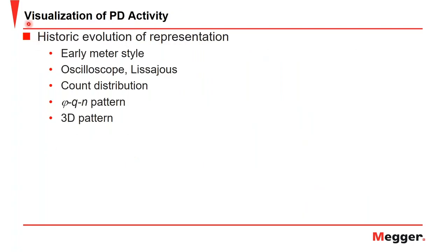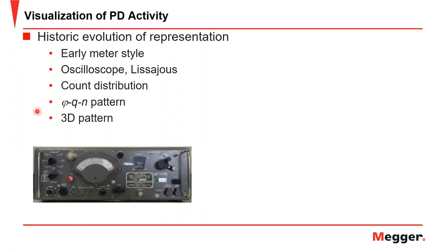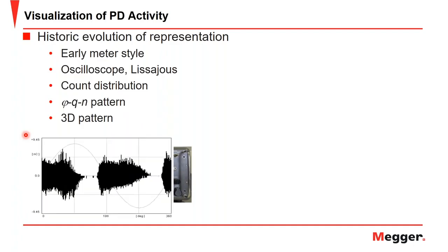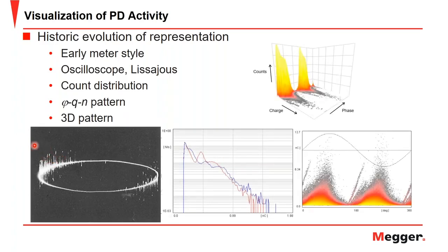Here we have visualization of PD activity, the historic evolution of the visualization. First, we have an old partial discharge meter or partial discharge detection unit, which would give you an analog measurement. And finally, we had the oscilloscope measurement, followed by the Lissajous measurement or visualization that made it possible to bring out symmetry between the positive and negative cycles. Here in the middle, you have your count distribution. And then here on the right, you have your charge phase count.